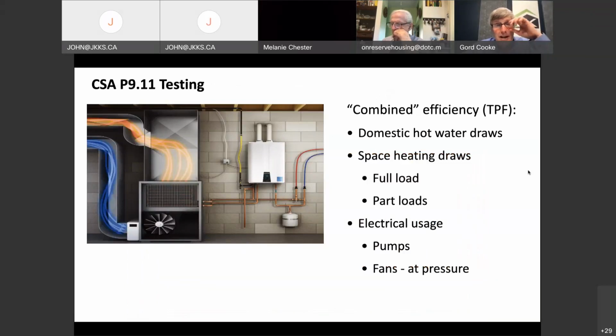It's important to understand these systems need to be matched, and there's a CSA standard for that. So if your community is buying or specifying these, always ask the manufacturer for their combined efficiency rating to make sure the water heater is properly matched with the air handler. It doesn't have to be the same company, but they have to show the two appliances were tested working together—that's the important part. For example, Navien is paired with certain air handlers, and Rinnai is paired with different ones. All of this assumes you have natural gas available to you.